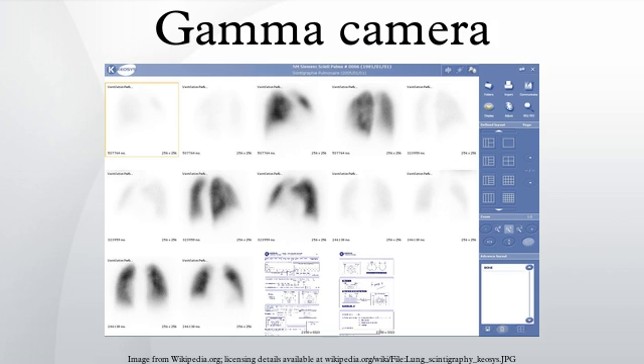A gamma camera consists of one or more flat crystal planes optically coupled to an array of photomultiplier tubes in an assembly known as a head, mounted on a gantry. The gantry is connected to a computer system that both controls the operation of the camera as well as acquisition and storage of acquired images.